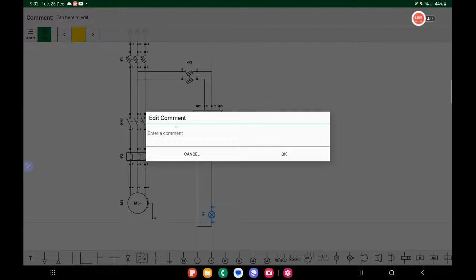But in the control panel, you will still need a source light that indicates you have power onto your control panel. So that would be the first thing we will put, a source light. Normally they are colored white or yellow. Since our background is already white, we will use yellow and name it source light.